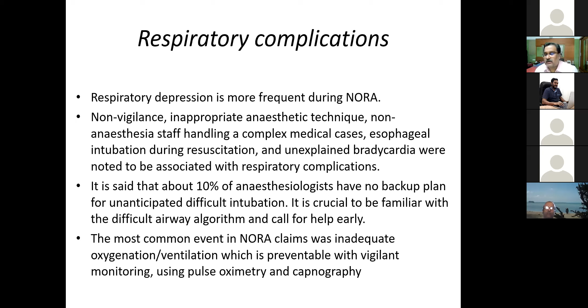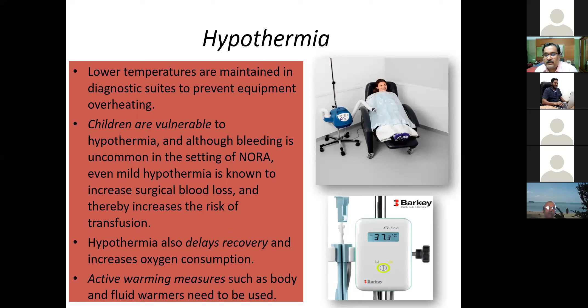The most common event in NORA claims was inadequate oxygenation and ventilation, which is preventable with vigilant monitoring using pulse oximeter and capnography. Hypothermia. Lower temperatures are maintained in diagnostic suites so that your equipment does not fail. And it is the pediatric population who are vulnerable to hypothermia. Although bleeding is uncommon in the setting of NORA, even mild hypothermia is known to increase the surgical blood loss, and thereby it increases the risk of transfusion also. Hypothermia also delays recovery and increases oxygen consumption. So you should have active warming measures such as body and fluid warmers in these areas, because the temperature is maintained quite low.